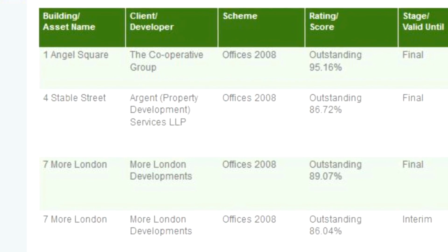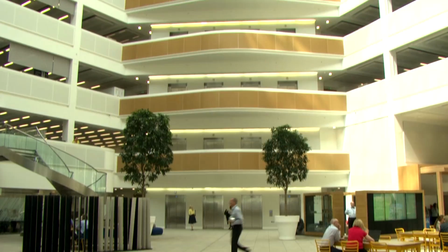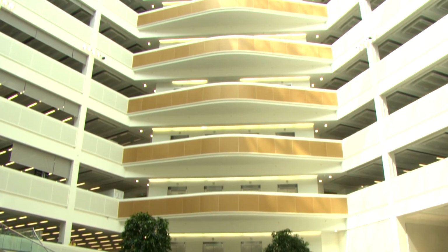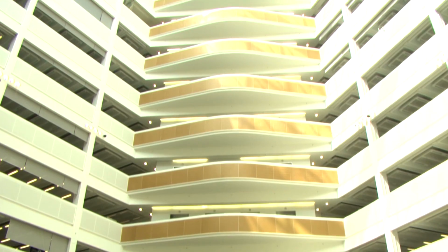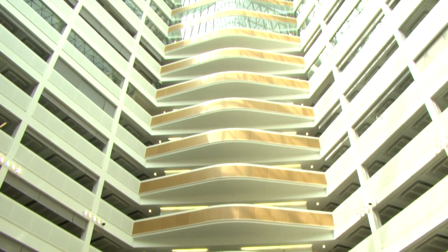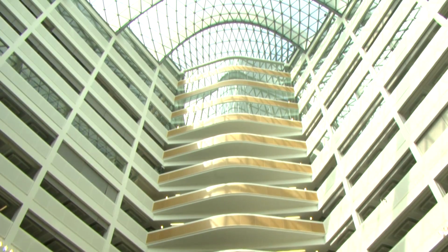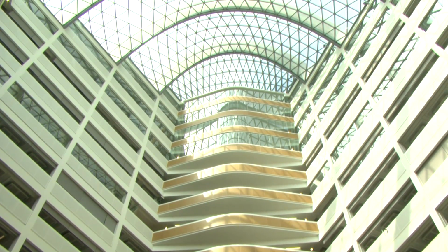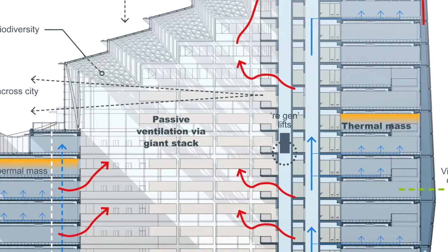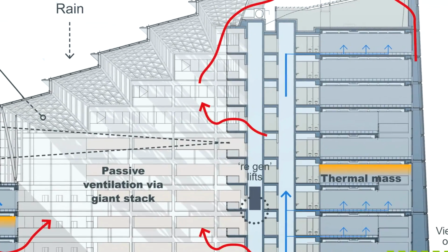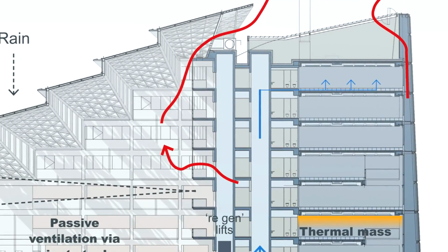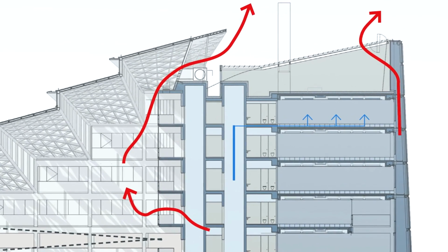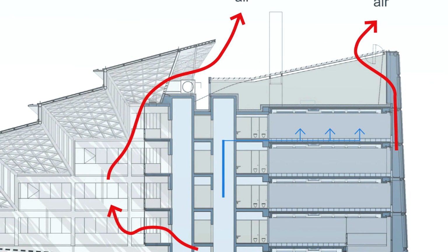Let's start then with the focal point of the building, the atrium. A key part of the design of this building is the central atrium, which we're standing in now. It's a 14-storey space around which wraps the floor plates. The atrium, from an engineering point of view, offered a number of opportunities which we've maximised in the design that you see. The first one is we use it as a large duct, for want of a better phrase, to allow the air to be exhausted. So the fresh air comes into the office floor plates through the floor and then makes its way out into the atrium and is exhausted at high level through the louvres that you see up at the top there.